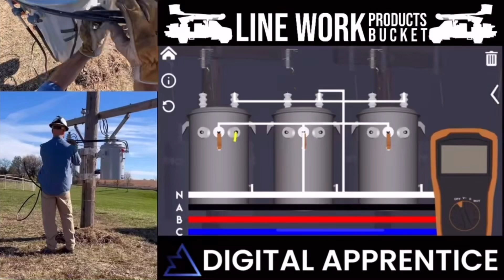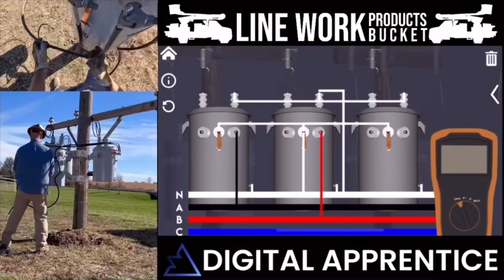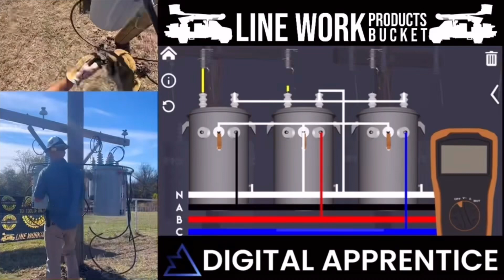So once I get all these hot legs in and tightened into that X3 bushing, then I'll start shaping my legs. But if we go back to this Digital Apprentice app on the right-hand side, you can see how I got all the neutrals connected. You got your tank grounds, you got your high side neutrals. Make sure all your high side neutrals are the same bushing. You don't want to mess up the polarity of these transformers, because then it can mess up a lot of things. It can mess these transformers up. So make sure you use the H1 or the H2 bushing across all transformers. So then you got to start dropping your legs down to every one of those phases, and next thing you know, you will have the correct voltage across all these transformers.